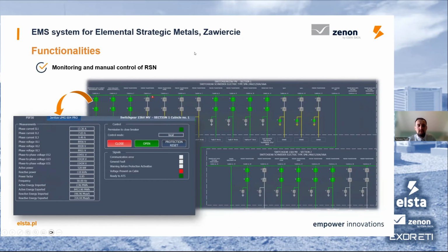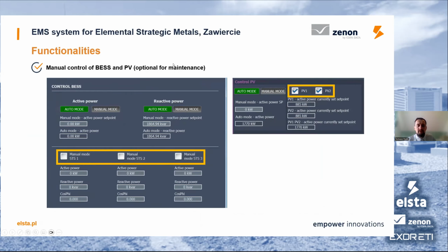We also introduced full monitoring of the medium voltage switchgear using the Zenon tools with automatic coloring, with pop-ups where we can gather all information, check the status, faults of every equipment, control them. So this is also one of the screens.